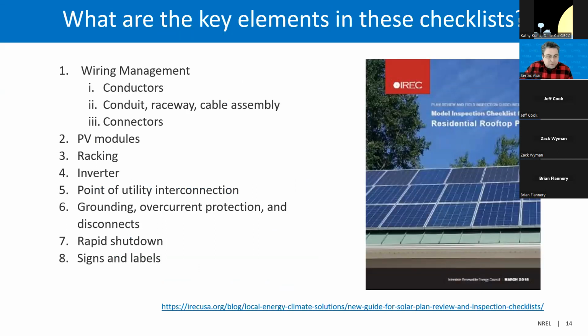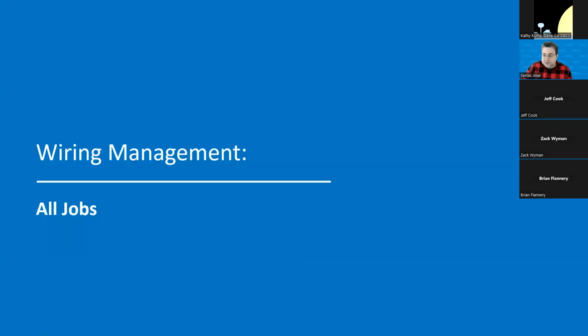And what are the key elements of these checklists? Despite the varying checklists, they have most of the same key elements relating to wiring management, which includes conductors, conduits, raceway, cable assembly, connectors, PV modules, racking, inverter, and point of utility connection, grounding, overcurrent protection, disconnects, rapid shutdown, and signs and labels. And in this training, we will be using the IREC inspection checklist to guide our discussion of the key elements to review across each of these areas. The first thing is the wiring management.